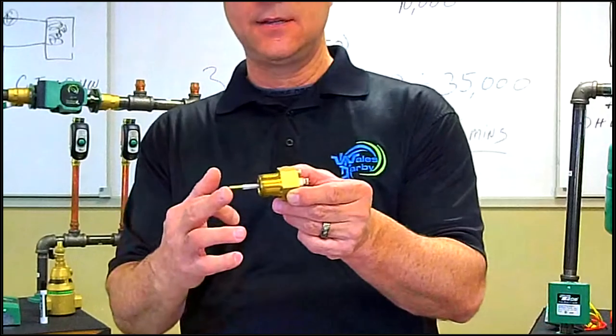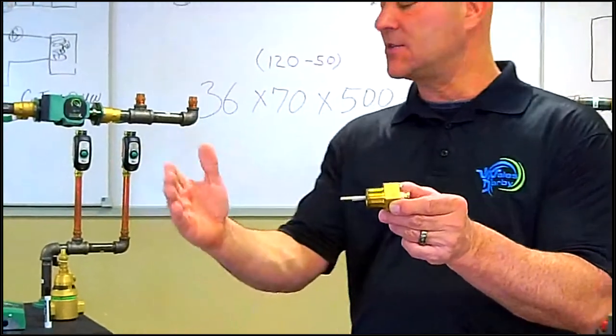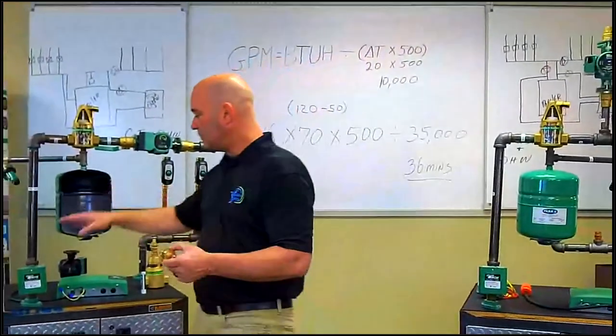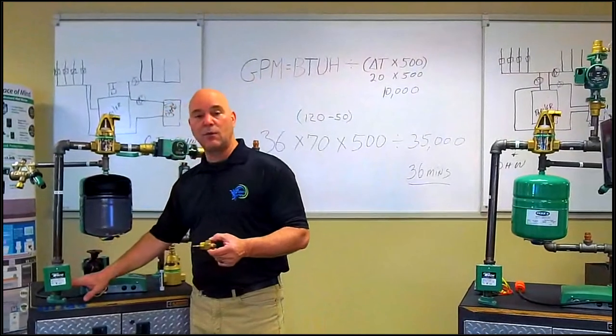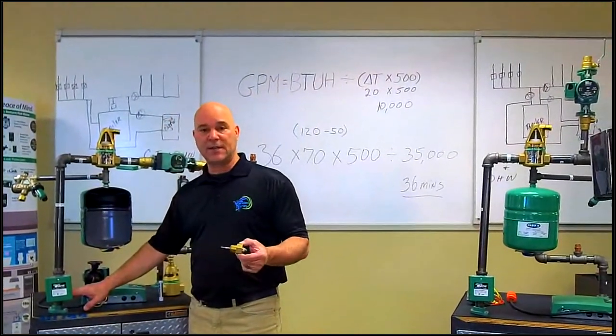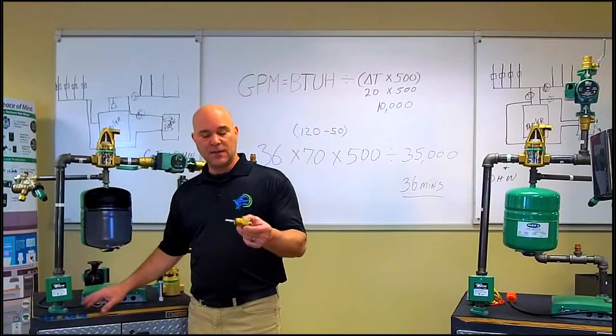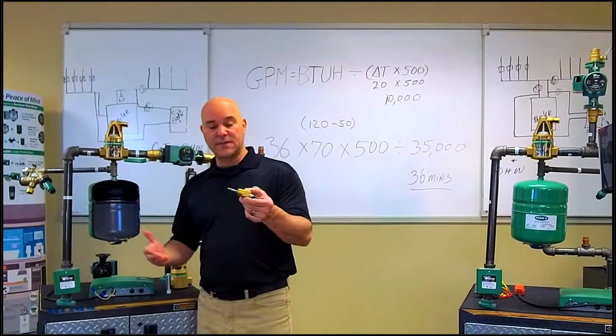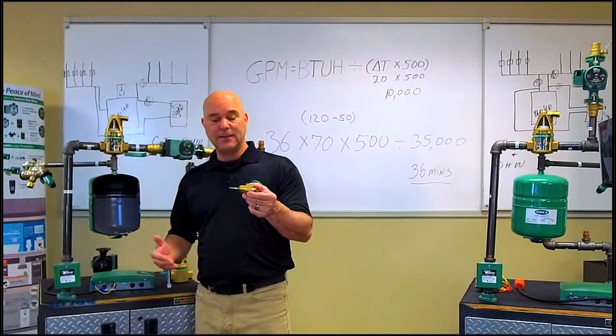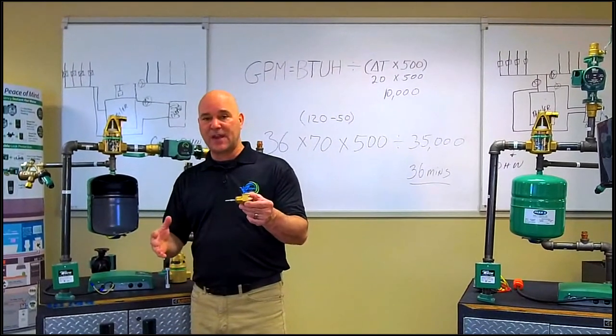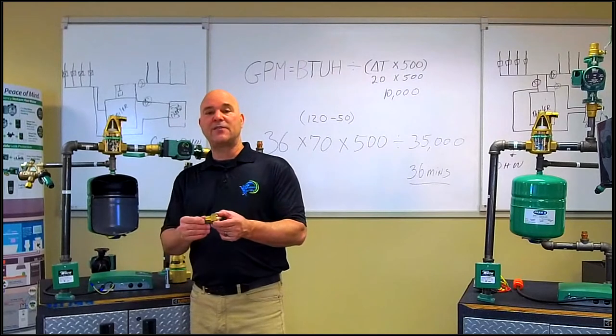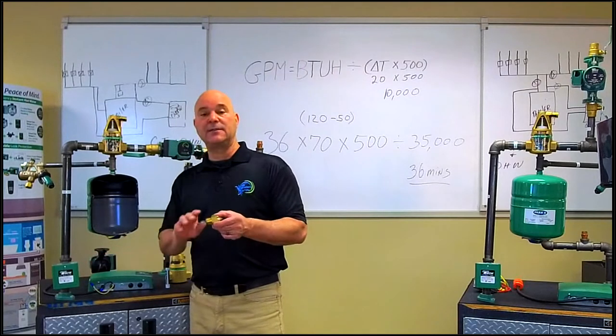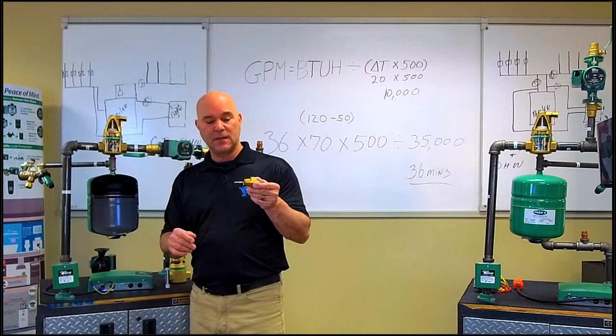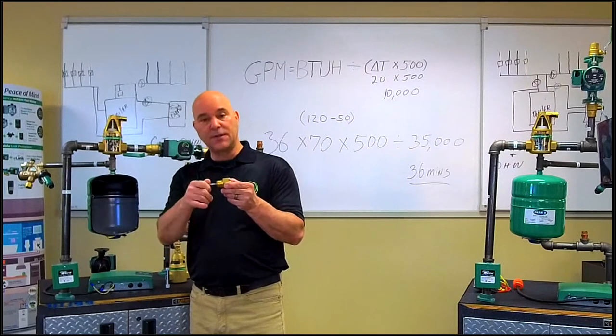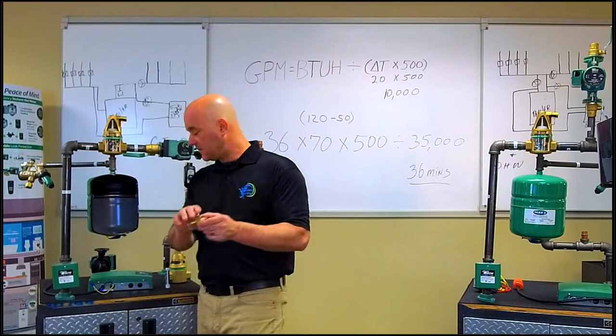And the reason you're testing it is you want to make sure that this is not touching the back wall. When we bring the water level down below the low water cutoff, the unit should shut down. This probe, over the course of its life, will have to be cleaned. Again, look at whichever manufacturer you're using, look at the manufacturer's guidelines on cleaning that probe. Because again, if this gets all corroded, it may not work properly.